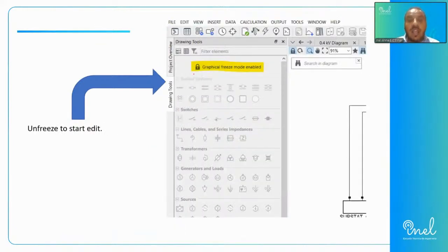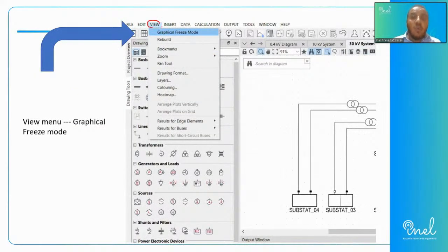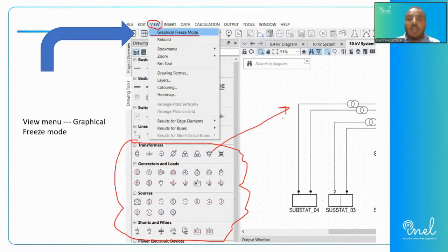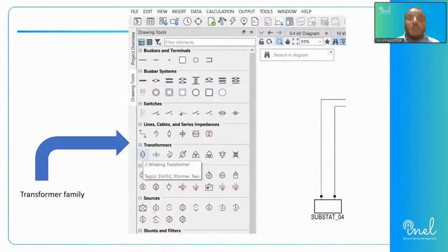So first of all, you will find some freezing mode, and you should unfreeze it using View. From the View drop menu, we will select graphical freeze mode, and from there you will find all components are now active. So you can insert any component. You can insert a transformer, a generator, a filter or a shunt element. Whatever component you need to add, you can add buses, for example. After unfreezing the drawing tool, you can drag and drop buses or generators or cables and so on.